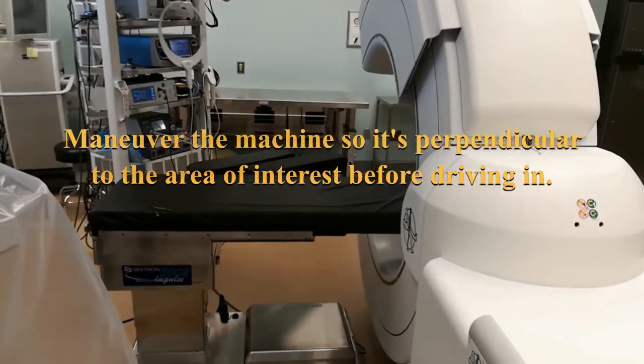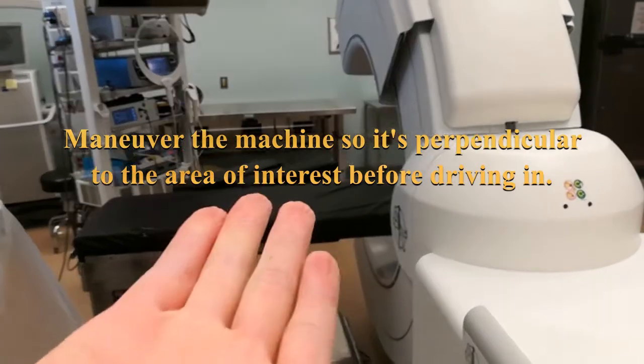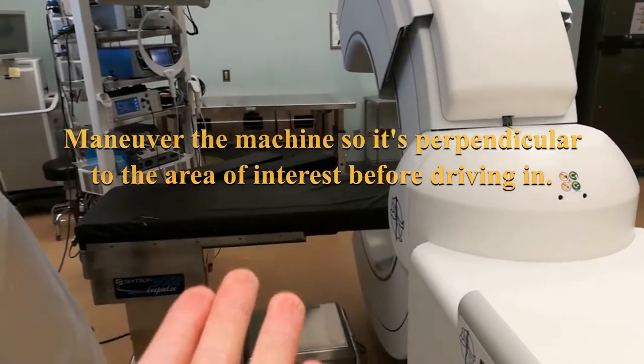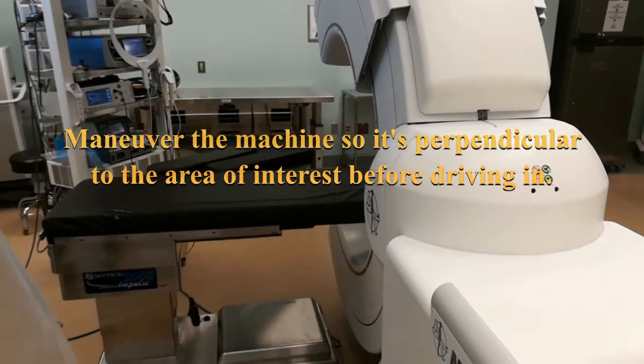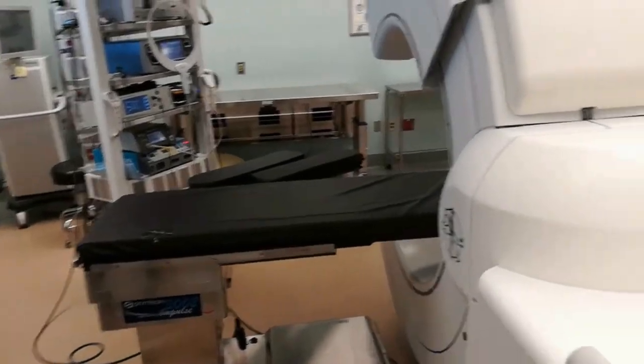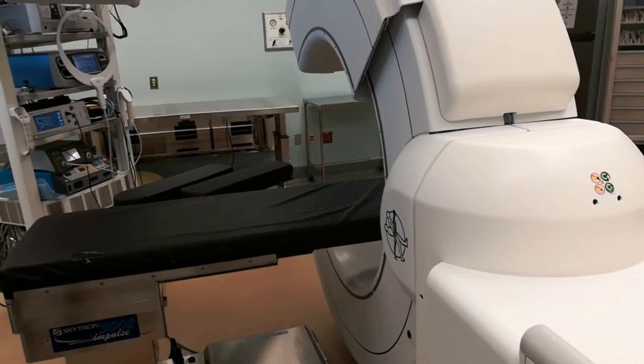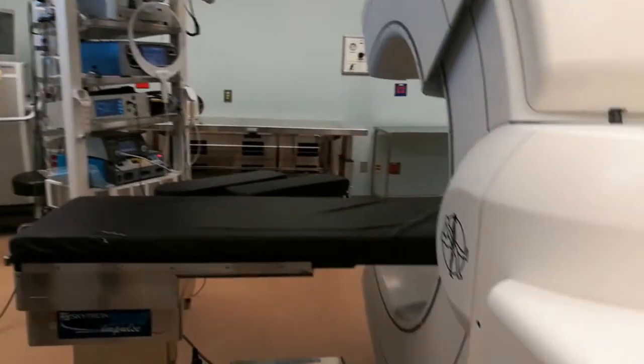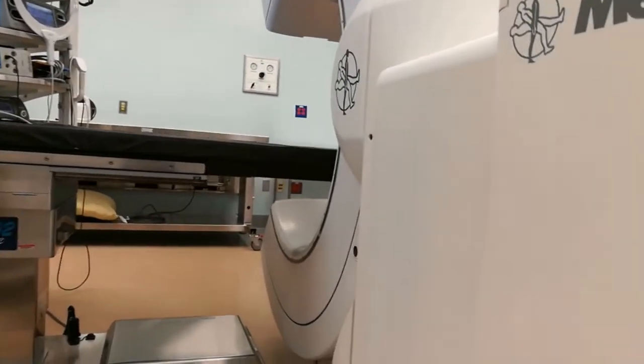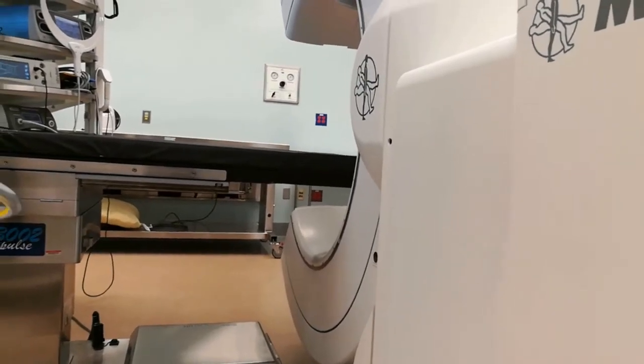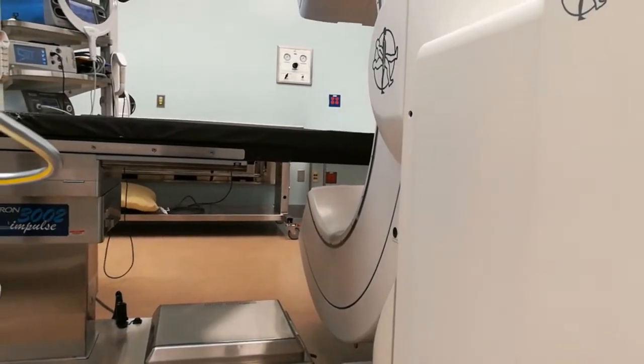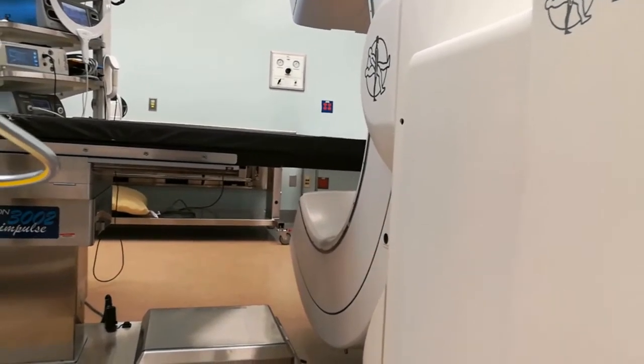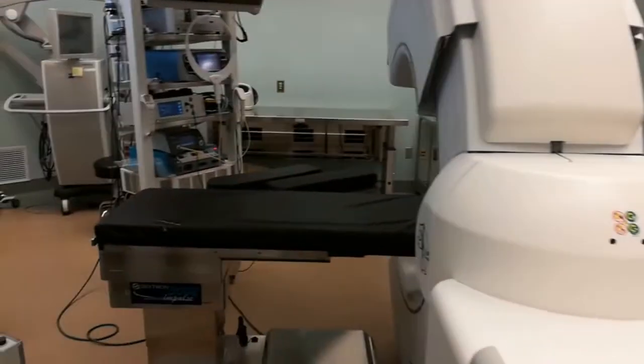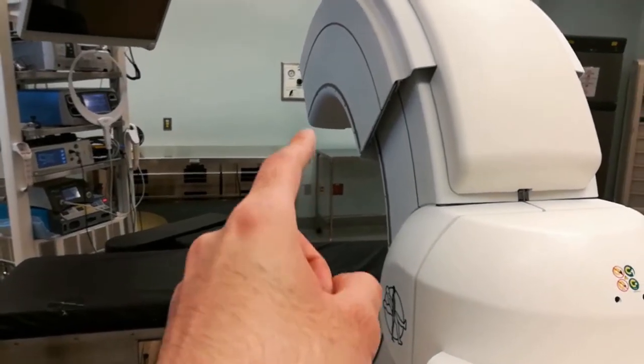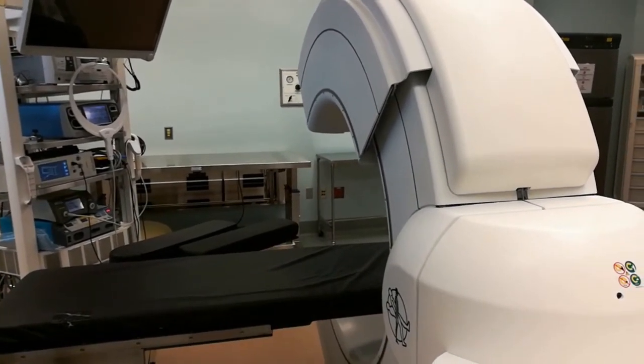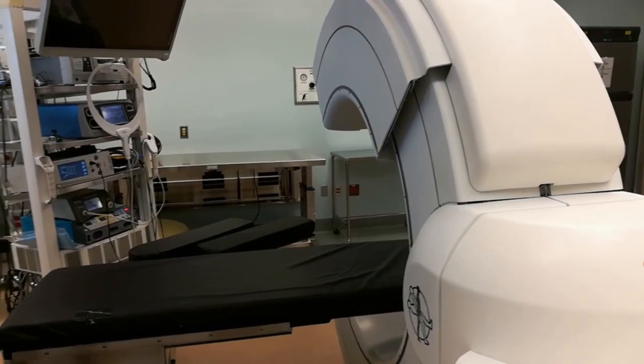But when you actually have to pull in on a live patient, the bed will be higher than this. If not, make them raise the bed, and it'll not be as clear as this. The patient will be wrapped up in a clear plastic wrap, like a cannoli. Just make sure to have either a coworker or someone else in the room spot for you as you're pulling in, to make sure you don't hit the bottom of the bed with the gantry. And then definitely get somebody to go on the other side before you close the gantry to make sure you're not going to amputate part of the patient or hit a piece of the arm board.